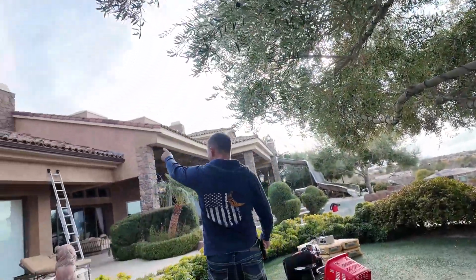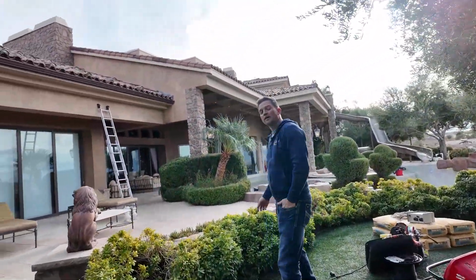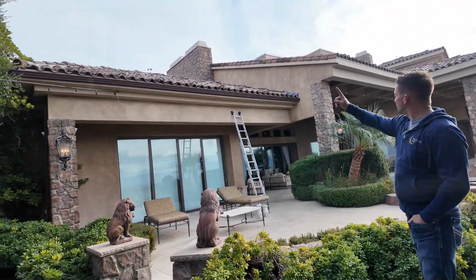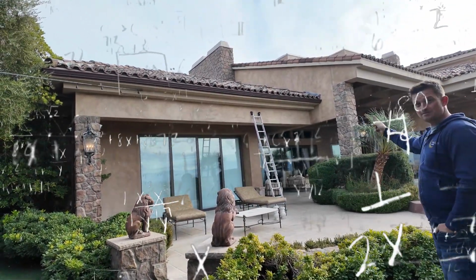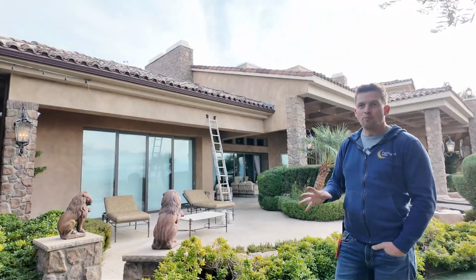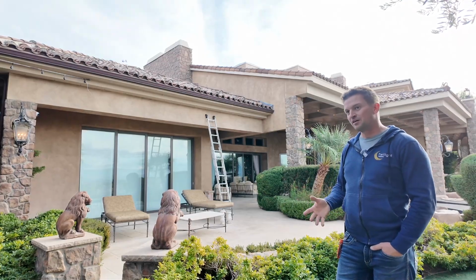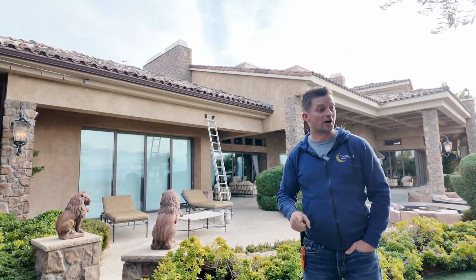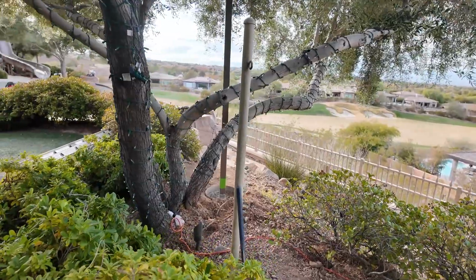There's 15 bulbs on this run here. They're 0.9 watts each. As we go to the second, third, and fourth run, it's going to be more than 15 bulbs. So I calculated that we've got about 70 watts. I'm hoping that we don't have much more than 30, 40 watts on the existing wire. So I'm going to come over here to the transformer.